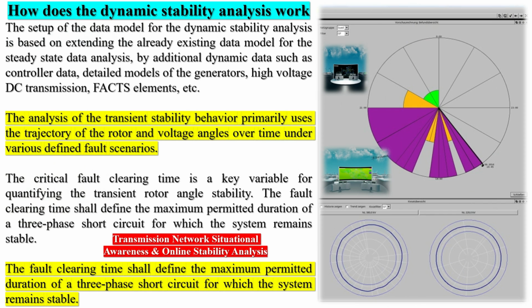How does the dynamic stability analysis work? The setup of the data model for the dynamic stability analysis is based on extending the already existing data model for the steady-state data analysis by additional dynamic data such as controller data, detailed models of the generators, high-voltage DC transmission, FACTS elements, etc. The analysis of the transient stability behavior primarily uses the trajectory of the rotor and voltage angles over time under various defined fault scenarios.